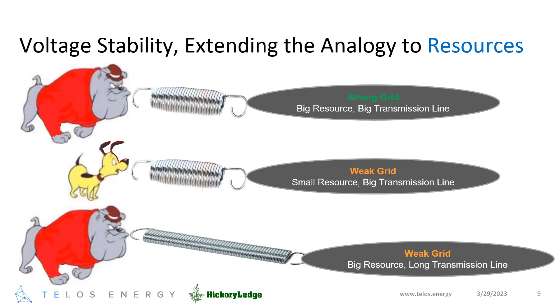Similar setup, but with a smaller resource: Chester, not as able to control voltage locally where he is. So if you jump on the trampoline, Chester's going to move a little bit more than Spike will. So you can have a weak grid there. By extension, if you have that large resource like Spike, who's very good at controlling voltage locally, yet you have a long transmission line to the rest of the grid, you can also have a weak system. In this way, we can start to differentiate between the resource types, their size, and how much effort they're putting into controlling their voltage.